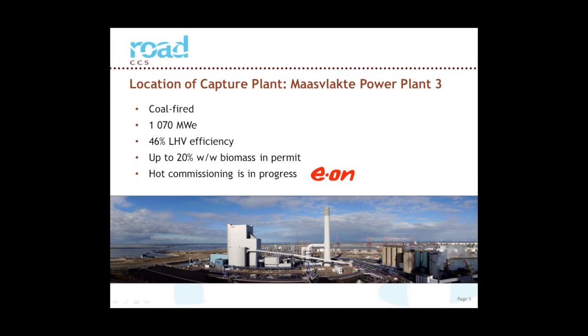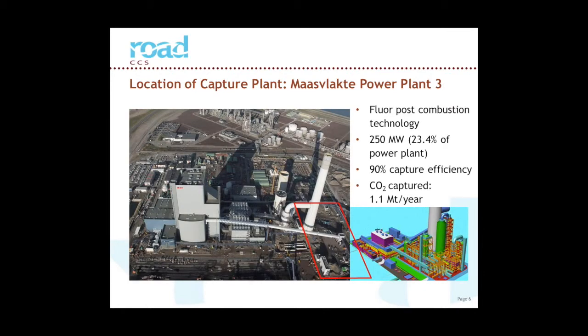So the power station's a big one. It's 1,070 megawatts roughly, net output, a little bit above 46% efficient, based on lower heating value, and that's partly because it has very advanced steam conditions, 600 degrees C, 620 steam conditions, and partly because of the direct cooling and low seawater temperatures. The average seawater temperature is about 12 degrees.